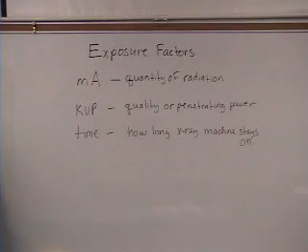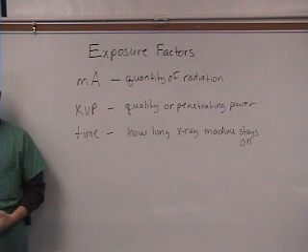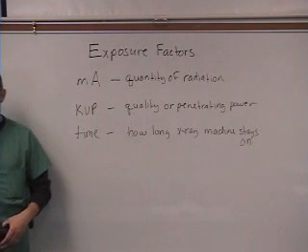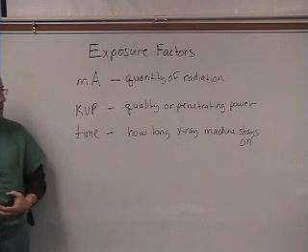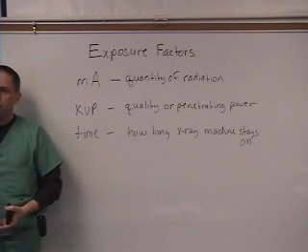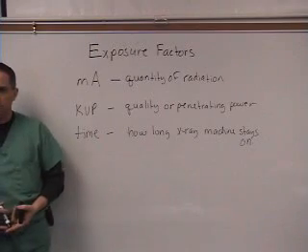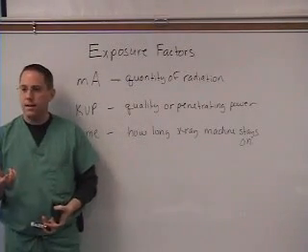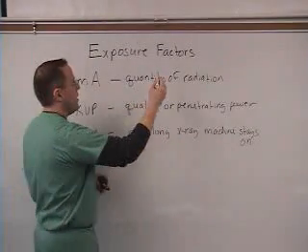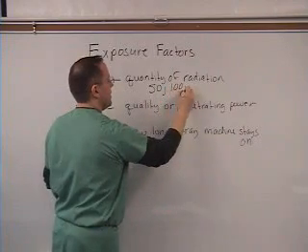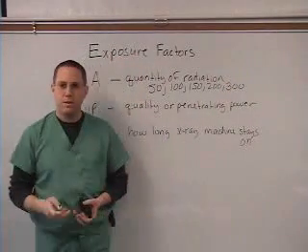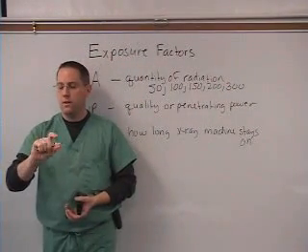There are three numbers you want to know about for the x-ray machine. When you go to take an x-ray, you're going to have to punch in some different numbers — it's sort of like programming the machine. The three numbers are MA, KVP, and time. MA is an abbreviation for milliamps; this measures the amount of radiation that you're producing. The higher the MA, the more radiation you're producing. Usually the settings for MA on the x-ray machine are 50, 100, 150, 200, and 300 — so you have about five choices.